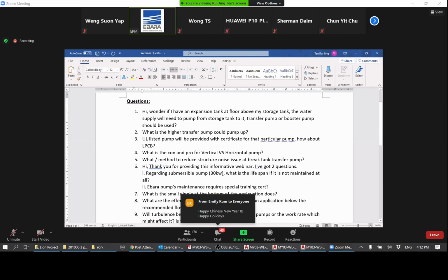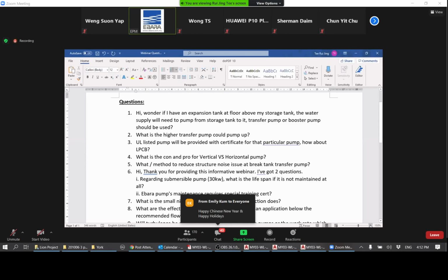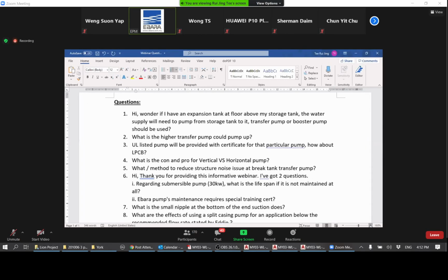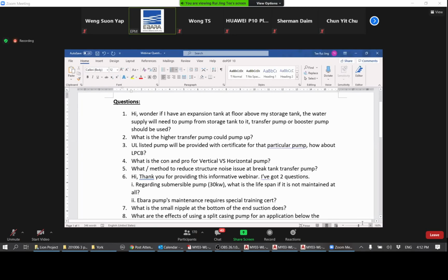The first question: I wonder, if I have an expansion tank at the floor above my storage tank, the water supply will need to be pumped from the storage tank to it. Should a transfer pump or booster pump be used? For water transfer, meaning that if you are pumping to fill up a tank, then you should just be using transfer pumps. Booster pumps are for pressure boosting to toilet fittings where you have variable demand. Transfer pumps are used to just fill up tanks, because when you fill up a tank, you just want to pump a certain flow rate to fill up that particular tank. So you don't need, let's say, pressure control. What you need is to ensure that the pump actually has enough head to pump water to that tank. So I hope that answers your question.